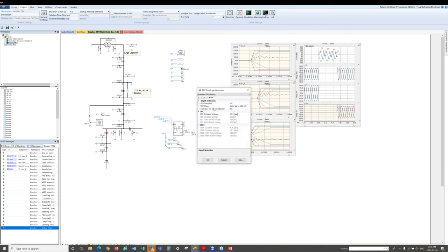Inside the component, you can go with IEEE or IEC. Now both of them are consolidated. They use the same waveforms. Therefore, you can select either one and you get the same result. As I said earlier, these are standard waveforms giving 100%, 60%, 30%, and 10% fault duties. But you can define your own, with the capability of interpolating those standard envelopes. So you can use both of them, IEC as well as your own. Or you can go completely user defined, which is specially provided for when you're getting information from the breaker manufacturer. If the breaker manufacturer gives you the capability curves, you go to user defined, and then you define the 2 points or 4 points in the capability curve, as I mentioned earlier.